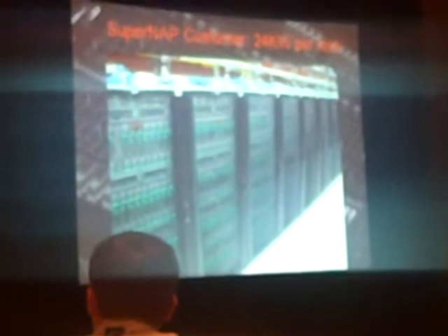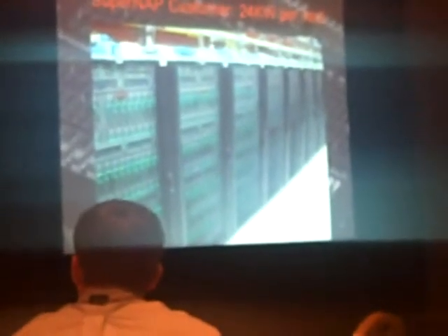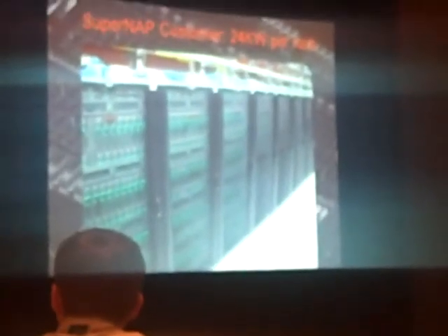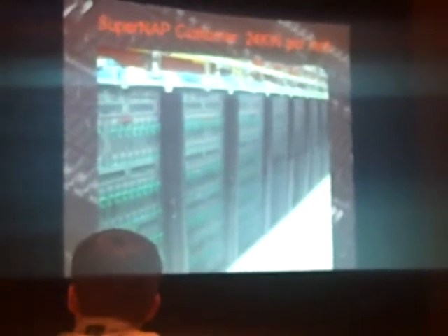One of the interesting things is that Sony PlayStation, when they first called us, said, well, we need 5,000 square feet. We said, okay, why do you need this much space? They said, because that's how much space we have to buy everywhere we go in order to get the amount of power that we want. And then, of course, we have to spread all of our racks apart at least 20, 25 feet to keep the air moving around to keep them cool. So we said, well, if you cram all your equipment together, how many racks would that take up? They said, about 40 racks. We said, wonderful, we'll sell you 40 racks. It'll take about 1,000 square feet. You can have all the power you want. Very easy calculation for Sony to run.